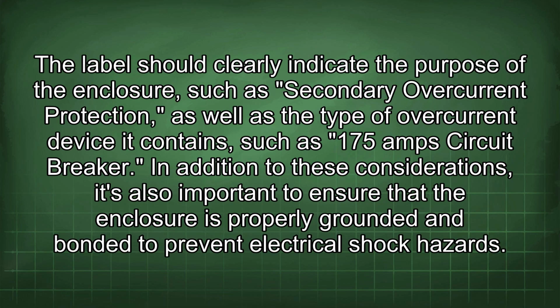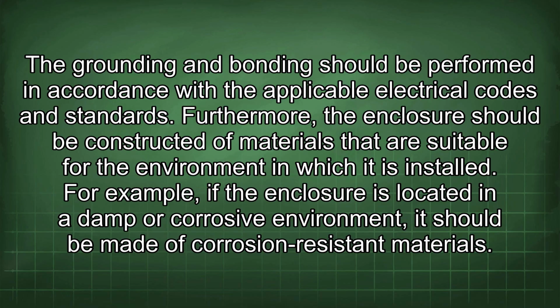The label should clearly indicate the purpose of the enclosure, such as secondary overcurrent protection, as well as the type of overcurrent device it contains, such as 175 amp circuit breaker. In addition to these considerations, it's also important to ensure that the enclosure is properly grounded and bonded to prevent electrical shock hazards. The grounding and bonding should be performed in accordance with the applicable electrical codes and standards.